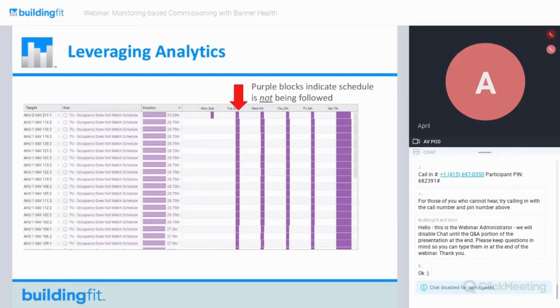They had a really old control system at all of the terminal units, and as we dug deeper, we found it was mysteriously resetting the controller cooling temperatures to 80 degrees at night. So no wonder they couldn't make it through the day — there's no way to recover from that.